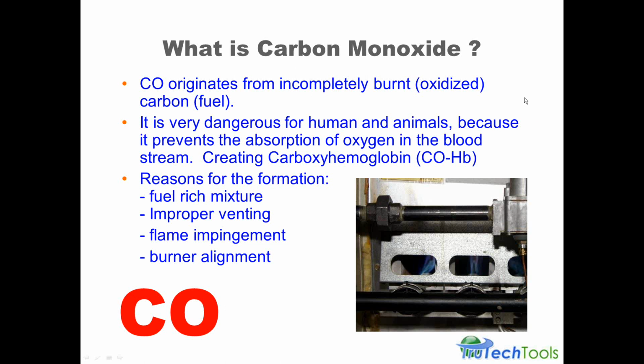Now let's take a look at what carbon monoxide is. We talked about carbon monoxide being one of the larger issues in terms of safety when it comes to combustion equipment. The CO comes, as we talked about just a few minutes ago, from incompletely burnt or oxidized carbon. So again, not enough oxygen for the amount of carbon present in the fuel. CO is very dangerous because it prevents oxygen absorption in the bloodstream, and it actually creates a new molecule in your blood. Usually you have oxyhemoglobin that's transporting oxygen around your system. CO actually binds to the hemoglobin and creates carboxyhemoglobin, or COHB. That is very dangerous because it disables the ability of your hemoglobin to transport oxygen around your body.